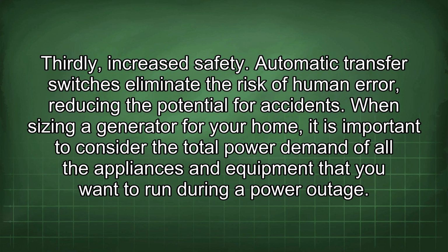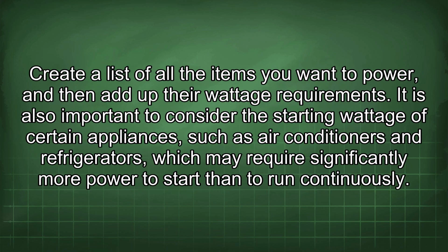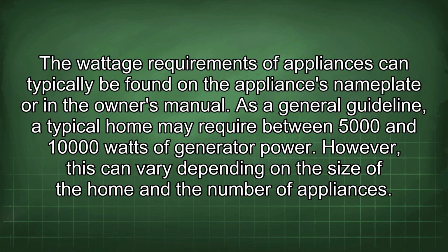When sizing a generator for your home, it is important to consider the total power demand of all the appliances and equipment that you want to run during a power outage. Create a list of all the items you want to power, and then add up the wattage requirements. It is also important to consider the starting wattage of certain appliances, such as air conditioners and refrigerators, which may require significantly more power to start than to run continuously. The wattage requirements of appliances can typically be found on the appliance's nameplate or in the owner's manual.